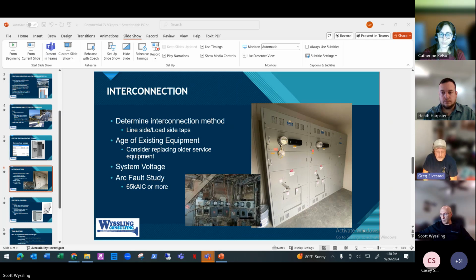Another issue related to commercial properties is arc fault studies. Sometimes, depending on the magnitude of a project, there may be arc flash studies as well, which are very expensive studies, and they're not always required, but those are orders of magnitude of 4 to 5 figures in expense, just because of the engineering expertise and the software that's required to do that. But arc fault studies, primarily because you want to make sure that the equipment you're specifying for the project is listed and rated for the appropriate arc fault interrupting capability. I mean, we've got 65K listed here. That's a common size for a lot of commercial properties. In some markets, it can be as low as 22K that you need a study done to make sure that the equipment you're specifying will withstand the fault.